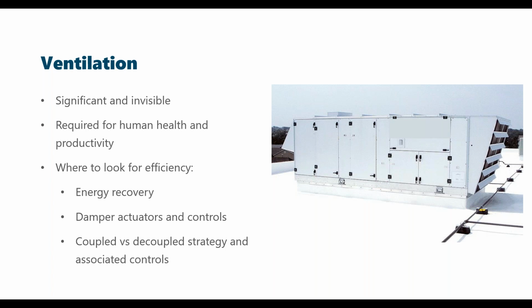It's required, and in terms of the measures that we look for around efficiency, they couple pretty similarly to the previous slide's measures that we talked about, but adding those measures of energy recovery and making sure that if there is energy recovery, is it actually implemented? I see so many energy recovery wheels that are put in and then they're just left in bypass. So again, there's this thought from the customer side of, I have an ERV section in my air handler, I must be saving energy, but it's making sure that that assumed strategy is actually what's taking place.